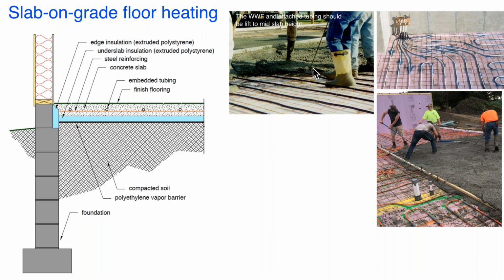One of the contractors has a lift hook, and what he's trying to do is get that tube and that mesh at approximately half the slab thickness. It doesn't have to be exact, but don't leave the tubing and that welded wire fabric laying on top of that foam. Structurally, the welded wire fabric is doing virtually nothing for you. And from a thermal standpoint, it does require higher water temperatures. We've done a fair amount of research in that area.